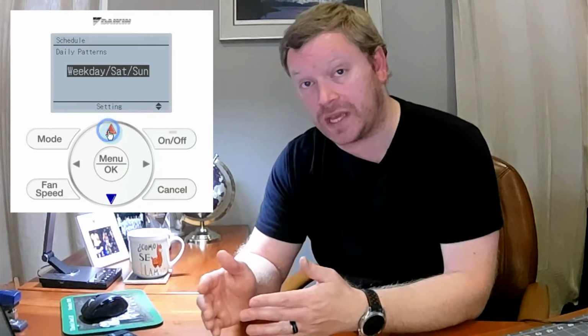Once you enable the schedule, you now need to pick your schedule pattern preferences. And what that means is, do you want the same schedule every day? Do you want a different schedule every day? Do you want a weekday weekend schedule? Do you want to split Saturday and Sunday off? Like, how do you want it set up? You pick. Once you've done that, the last thing you need to do is you need to change the actual schedule settings. So go back into schedule. From the main screen, go down to settings, and here's where we're going to set up the actual schedule.